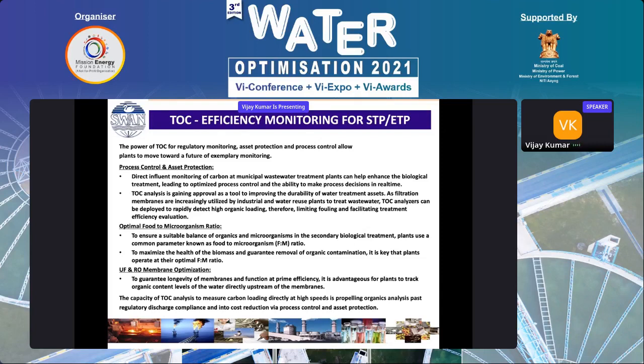It has advantages for plants to track the organic content level of water directly upstream of the membranes. The capacity to measure carbon loading directly at high speed is propelling organic analysis past regulatory discharge compliance into cost reduction via process control and asset protection. My message today is that TOC is a very good tool for you as a water quality index. Periodically check your water resources quality, then see at different stages of water treatment whether TOC is getting down or not.